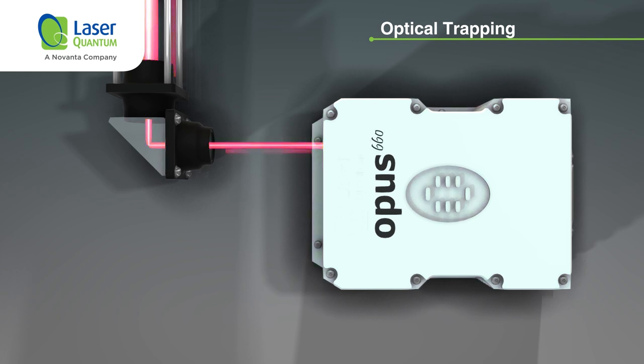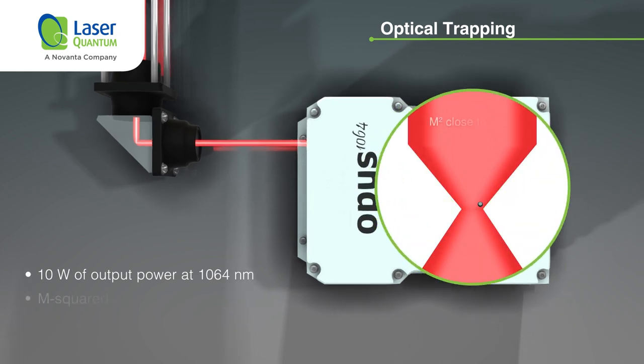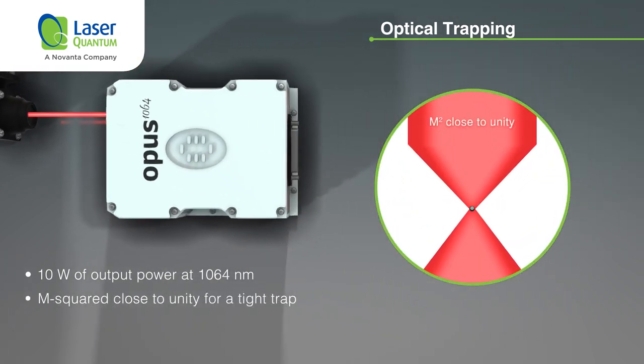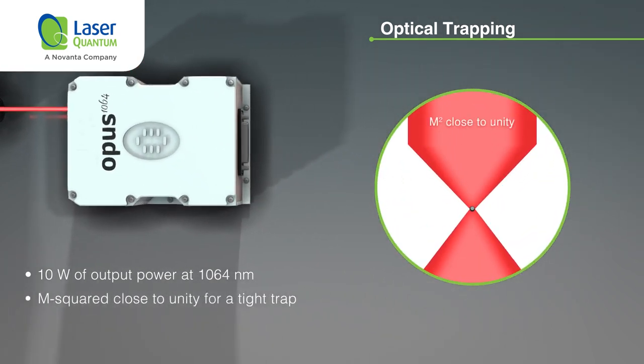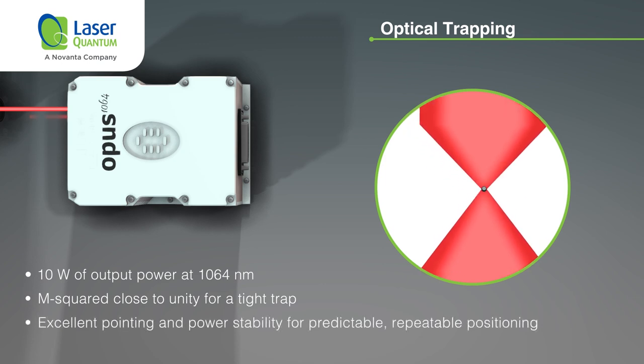The wavelength choice depends on the sample — low absorption is key to prevent sample heating and damage. The OPUS 1064 is available at up to 10 watts of output power with an M² close to unity, enabling a tight trap.